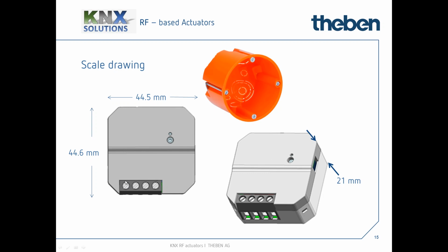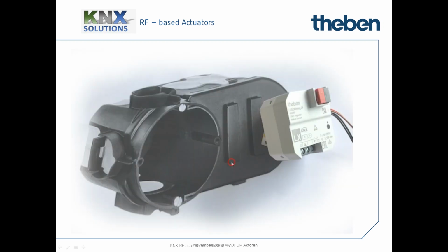You discover one screw terminal here. In comparison to other manufacturers offering flush mounted actuators, we decided to keep these terminals because it's better in regards of space in the junction box. Otherwise you'd need dominoes or Wago terminals to link cables together, which takes space. So we decided to skip that, and you apply the cabling directly, which is better for the spacing in the junction box.